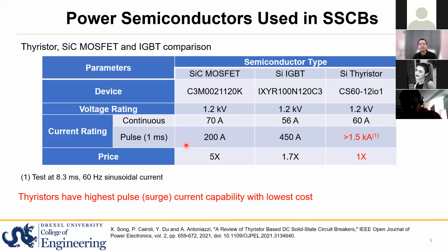However, if we look at their pulse current application, which is what we consider in a DC circuit breaker application, because there we not only look at continuous current but also pulse current capability, we can easily see that thyristors are much higher than MOSFET and IGBT.